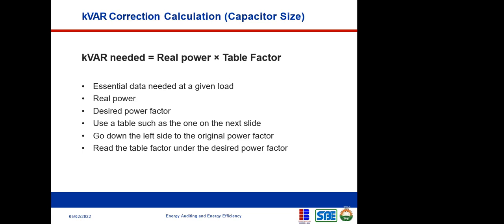The real power is also needed, and you also need to know what your desired power factor is. For example, if you come to a facility and the power factor is 70%, and you want to correct that power factor to 90%, you need to know the actual power factor of the facility and the desired power factor. If you know this and you know the real power, you use a table.